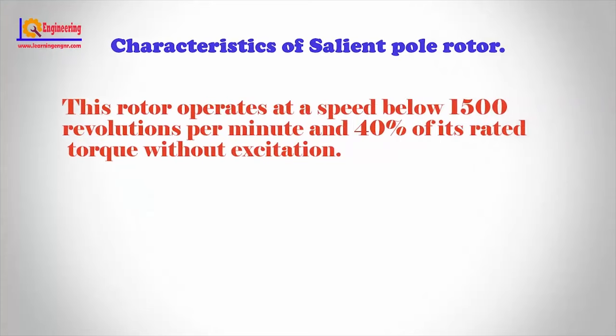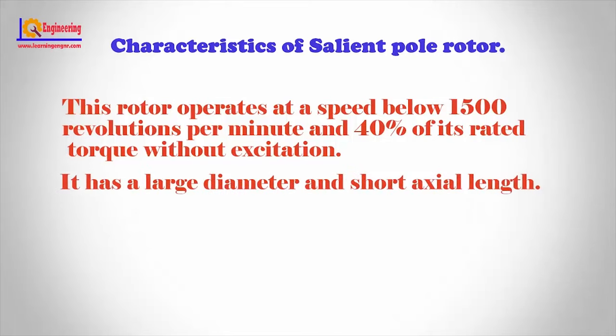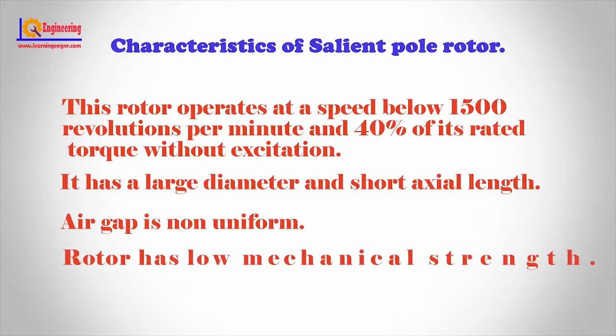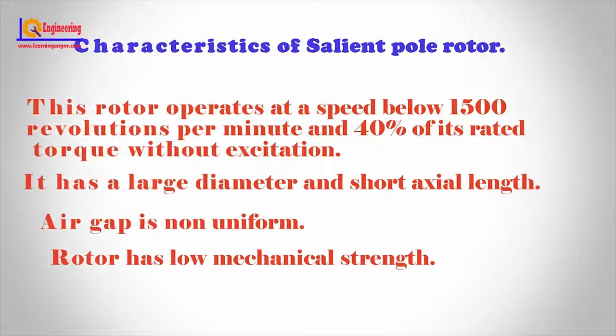Characteristics of salient pole rotor: This rotor operates at a speed below 1500 revolutions per minute and provides 40 percent of its rated torque without excitation. It has a large diameter and short axial length. The air gap is non-uniform, and the rotor has low mechanical strength.